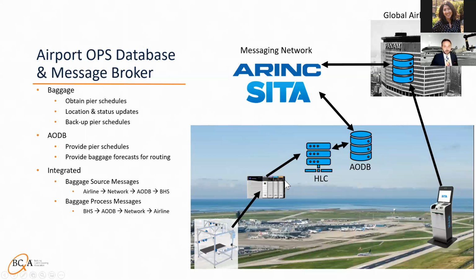As bags go through the system, they go under automatic tag readers, and then those will send the bag tag read to the PLC, to the upper level controls, and to the AODB through the messaging network and back to the airline. And those are called baggage process messages. Those ones let the airline know when the bag has hit different parts of the system and that it's on its way to the pier. This will allow airlines to know if there's bags that might miss the flight or if there's ones that have been pulled from the system for various reasons.